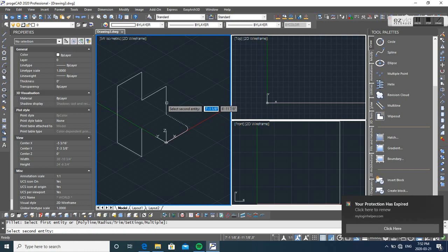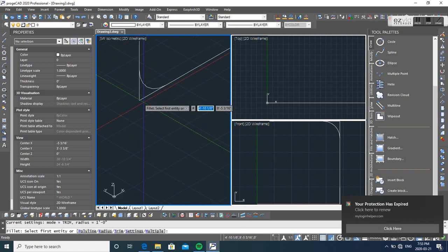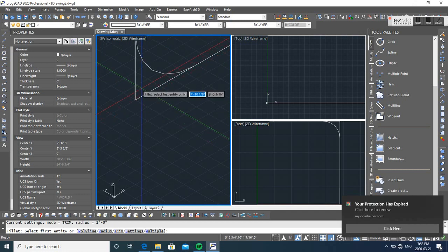But I will show you a minimum of 12 inches radius, and that's a standard bend, because most of the tools, of course, you're using a tool to bend a rigid conduit, a rigid steel, or an EMT, or any like PVC or something. There's of course a minimum radius.